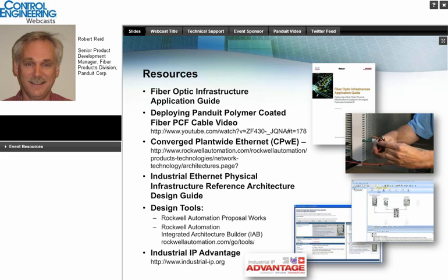Could you address termination or patch panel selection? Cabinets appear large for what's in them. Is there a less intrusive way to do that? There are patching facilities where there's not a lot of real estate in those boxes for cable management. In particular, there are standards on the minimum length of patch cords. So especially on the copper side for 1 gig, you do have to manage those patch cords. You do have to store slack of the patch cords on the fiber side. You can't basically make right angles with the cable. So it appears as though there's a lot of wasted space, but it is to protect the fiber and to protect the copper.